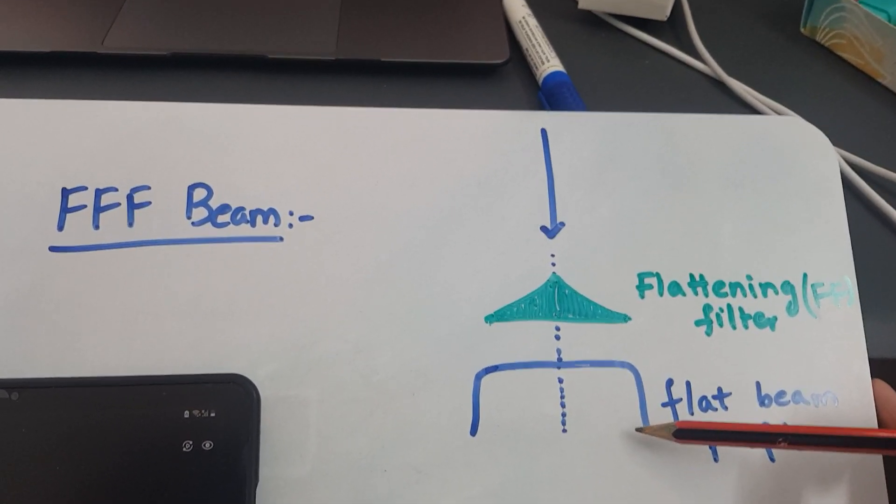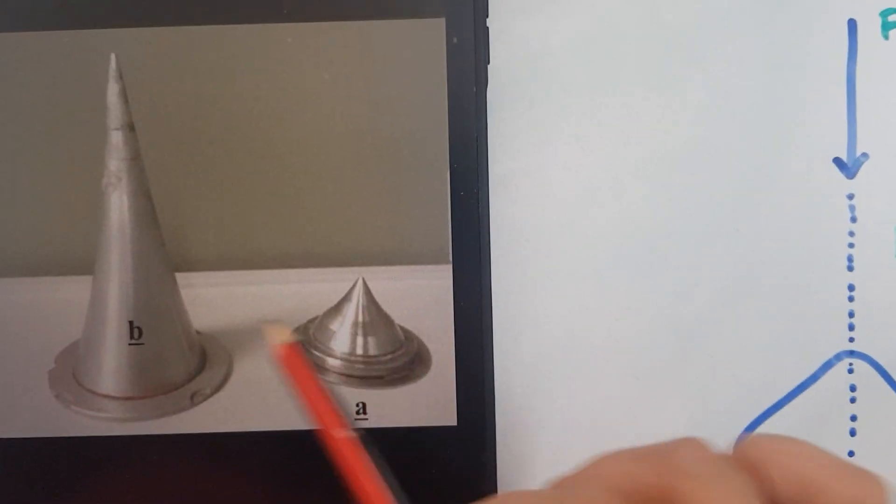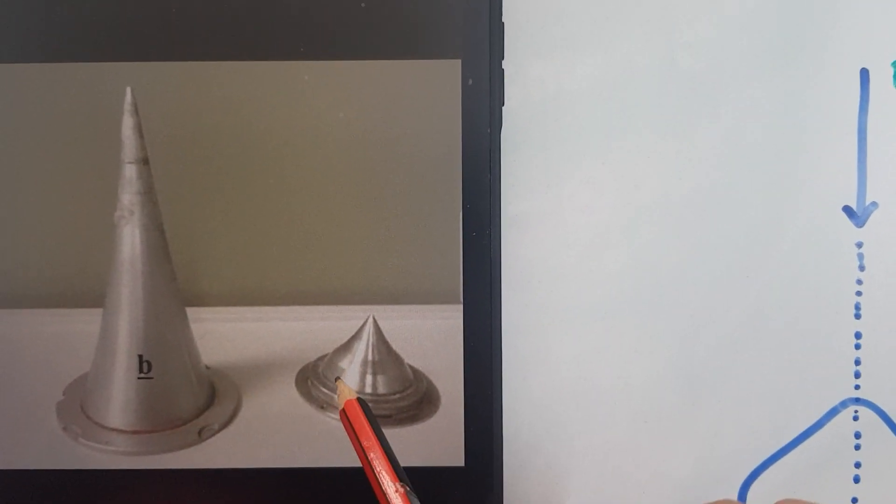This is how a flattening filter looks like, here thicker and here thinner. And this is without the flattening filter. Flattening filters, based on different energies, you can use different types of flattening filter based on different energies.